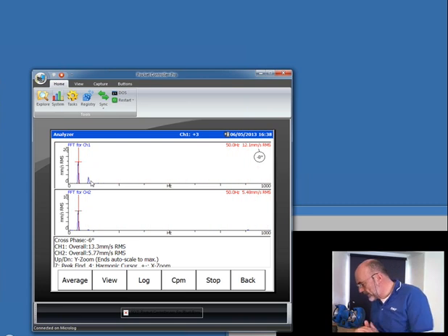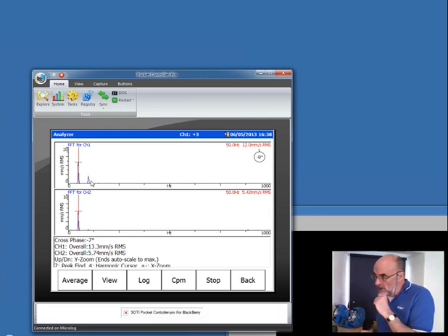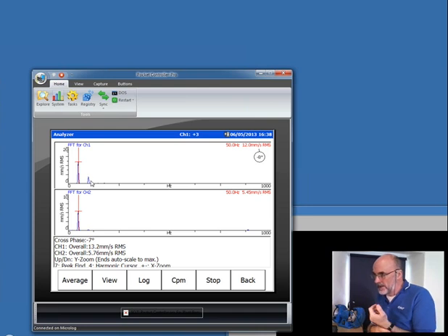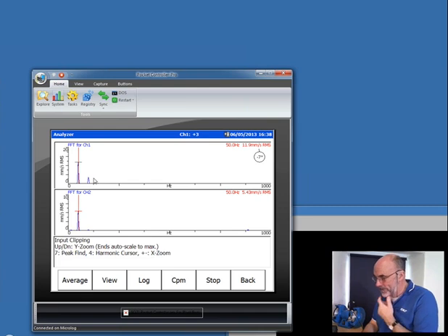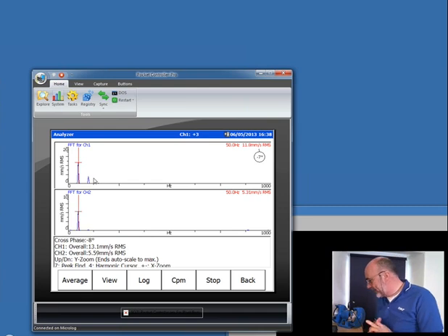And this leads into a nice little demonstration of an electrical problem. Because what I've got here is a high 2 times. In the UK, where the supply frequency is 50 hertz, that would be 100 hertz. What I'm going to do in a second is a switch-off test, another classic test that you do when you're harvesting evidence for your diagnosis.